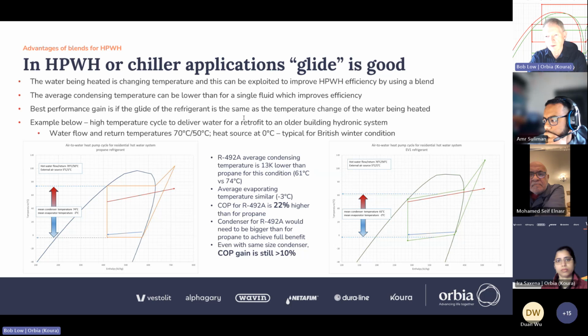Whereas you go to 492A on the right, exactly the same terminal conditions for the source and sink fluids, but now the cycle is running between -3C and +61C. So we've dropped the average condensing temperature by the difference between 74 and 61, 13K. That makes a big difference to the overall performance. And you can see here, if you do follow the numbers through, then you would get a 22% higher COP than with propane. Now, what's the catch?